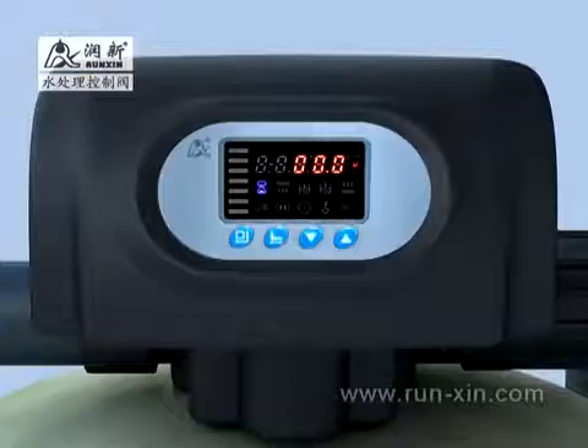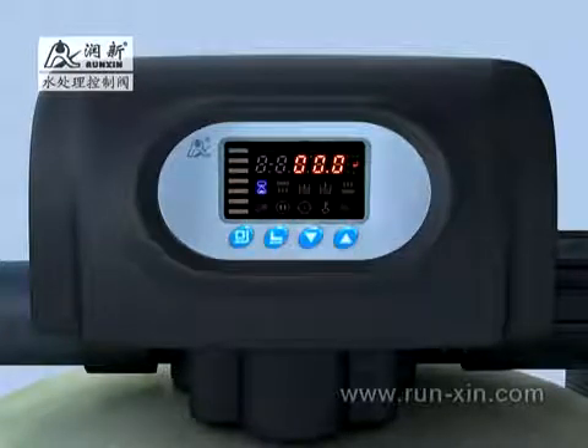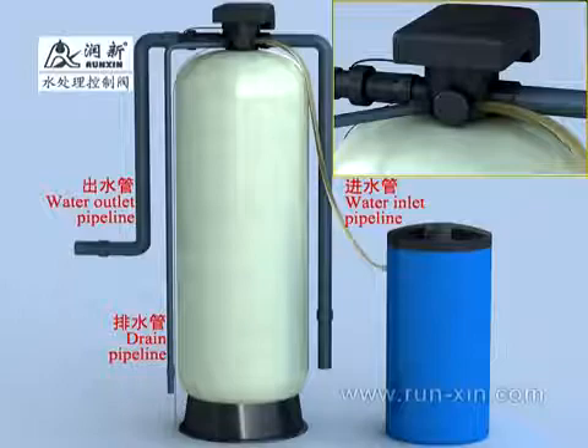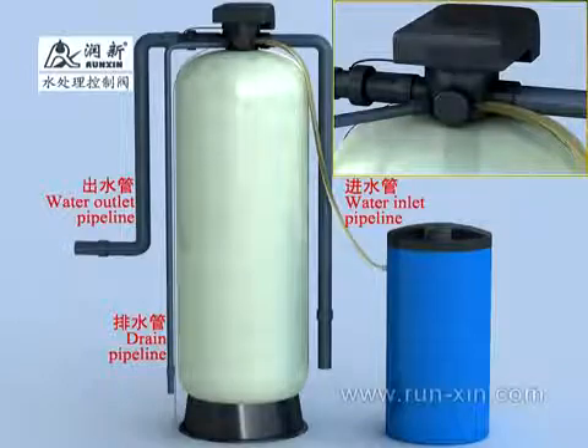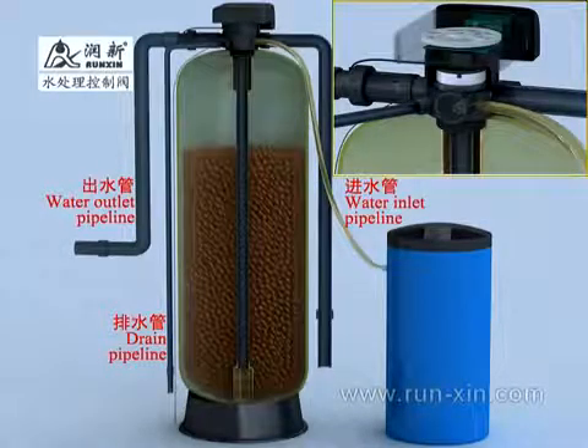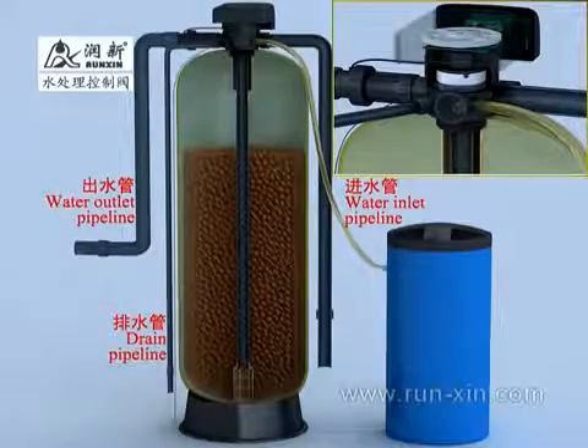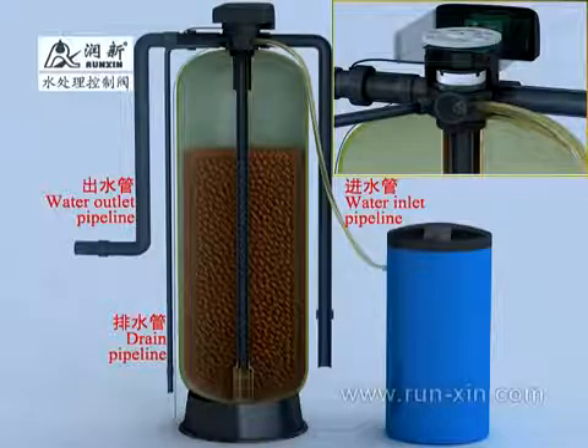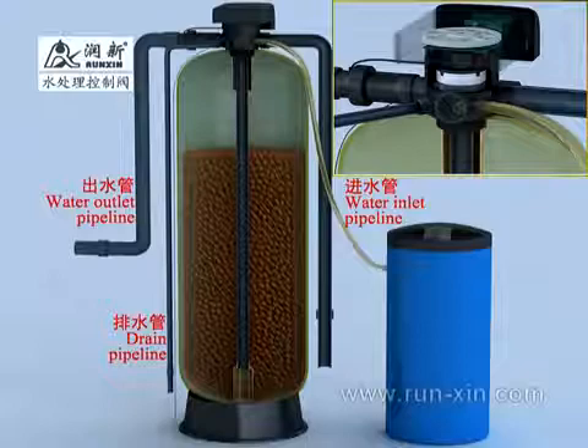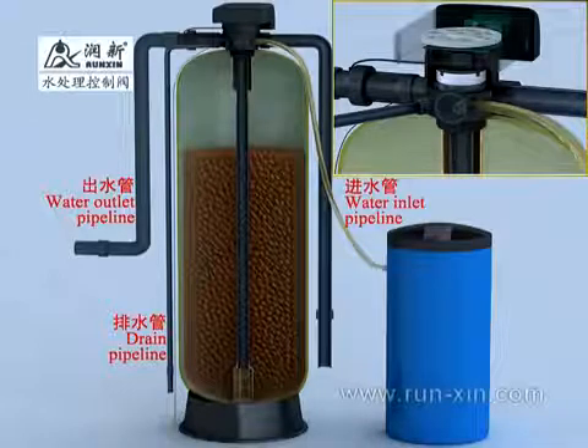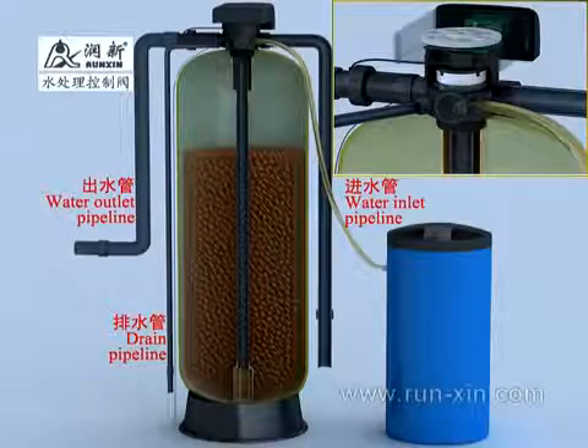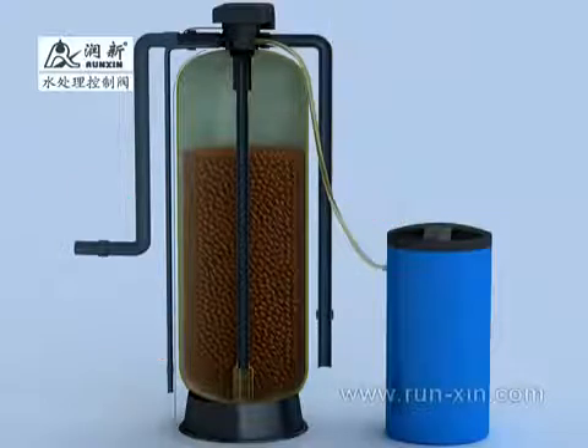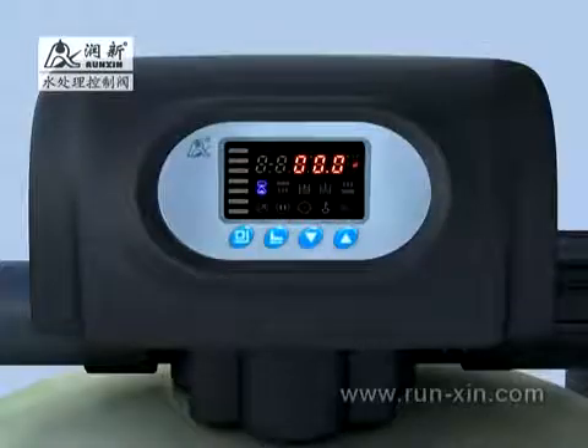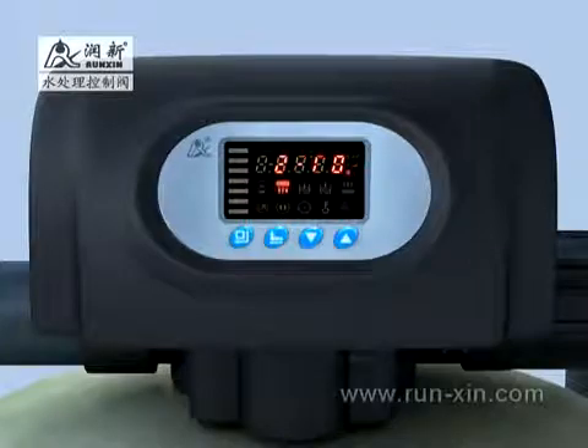When the service flow rate reduces to 0, the system starts to regenerate. The motor controlled by the main control board drives the big gear to rotate, and also drives the moving disc, which is fixed with the shaft. With the change of relative angles of the moving disc and fixed disc, the flow channel has been changed. When it arrives at the backwash state, the symbol of backwash state lights.